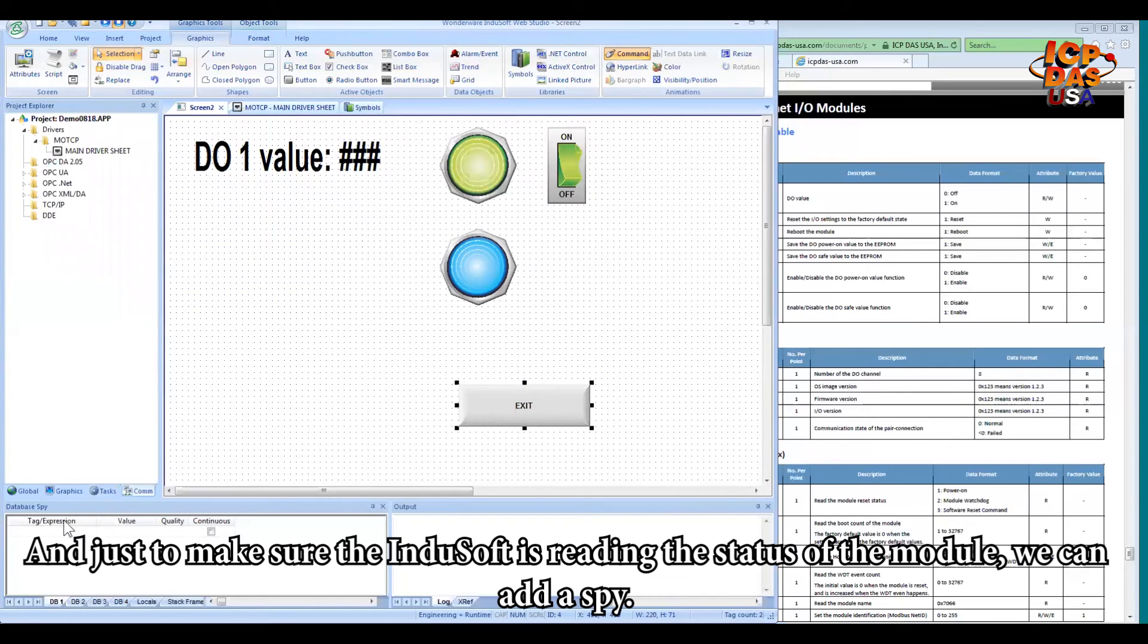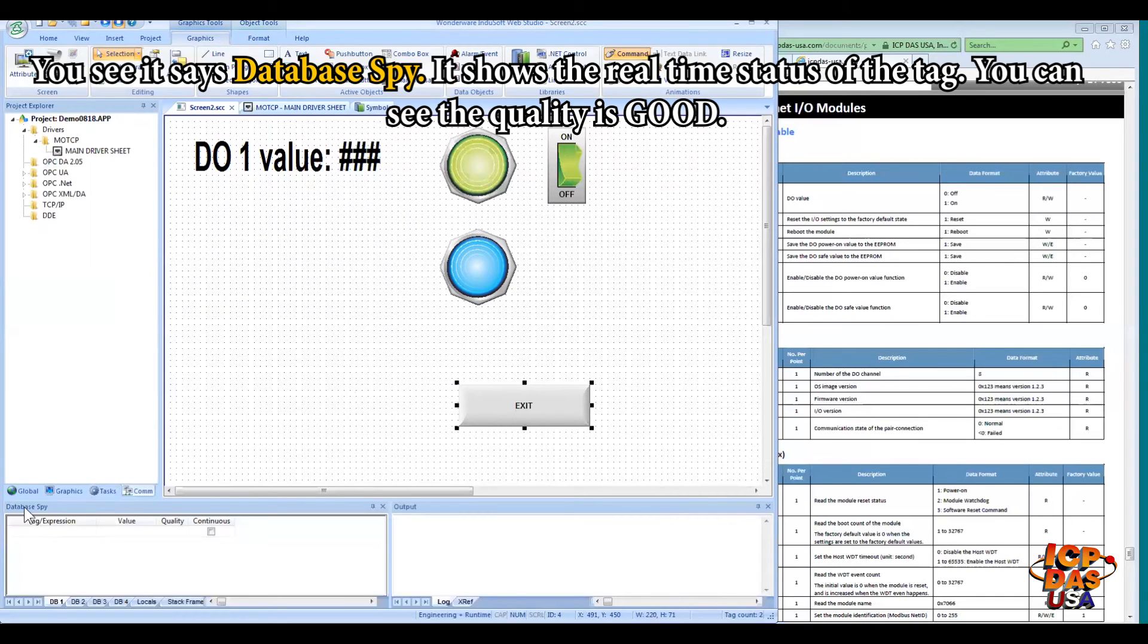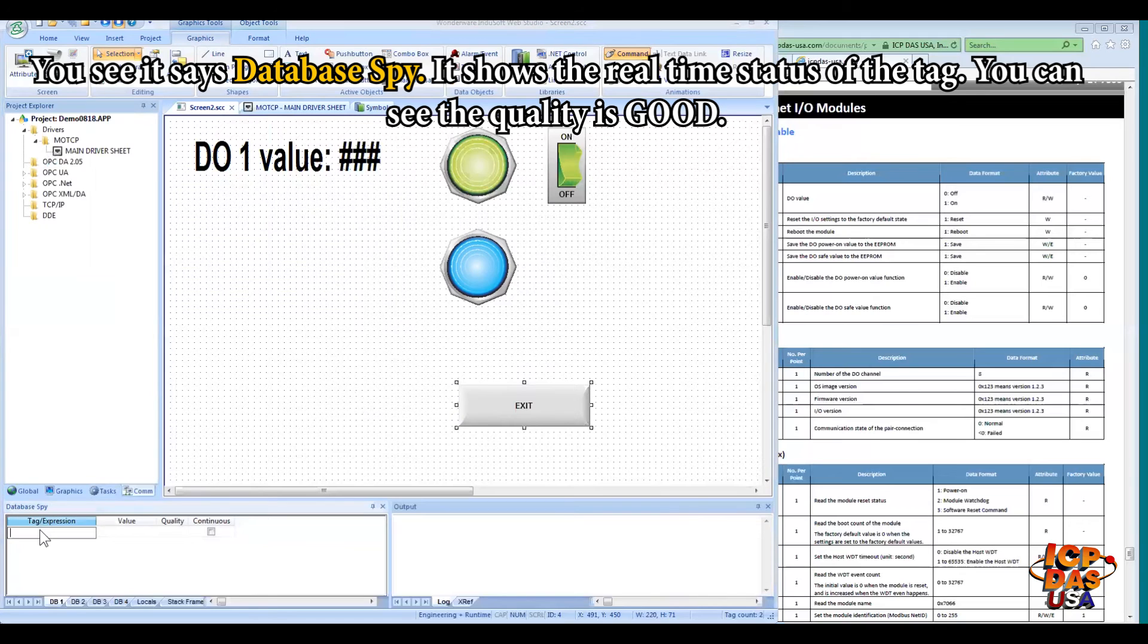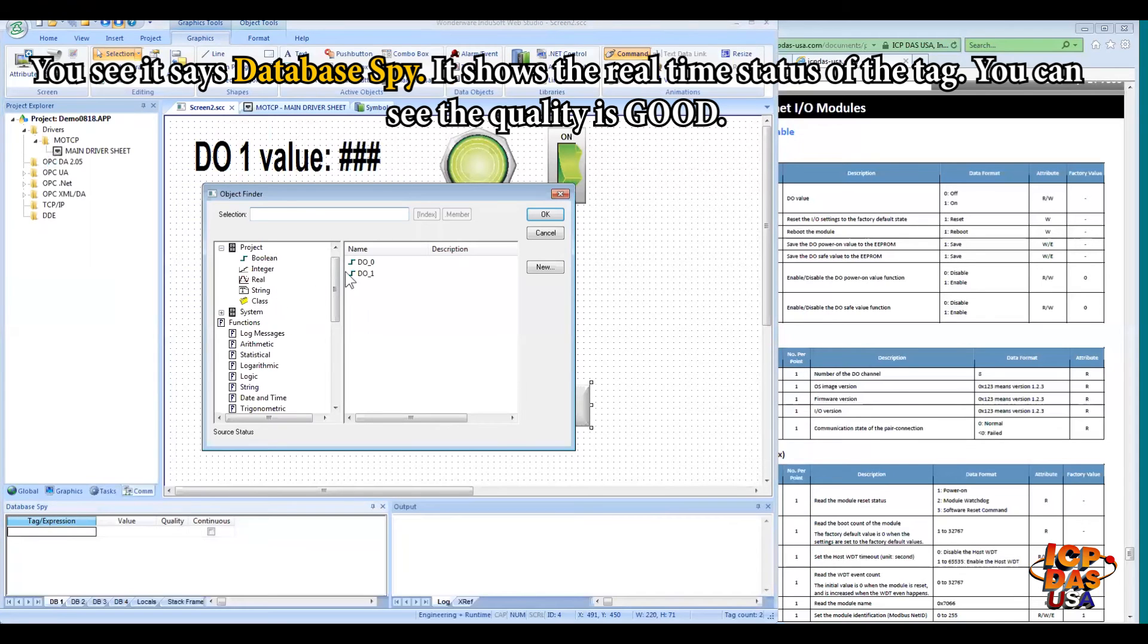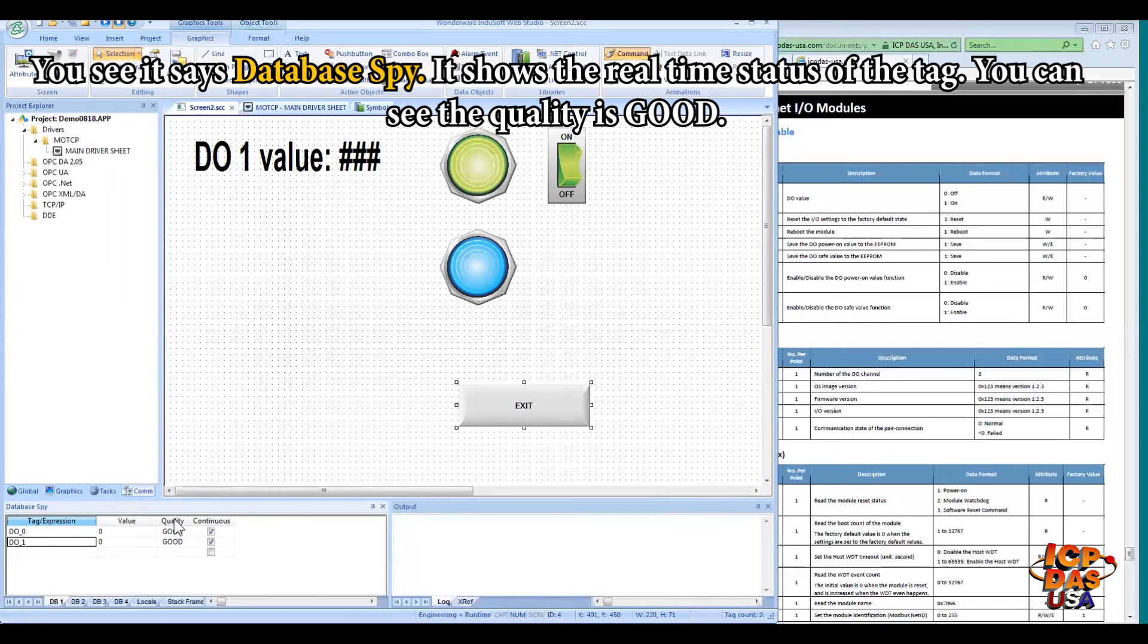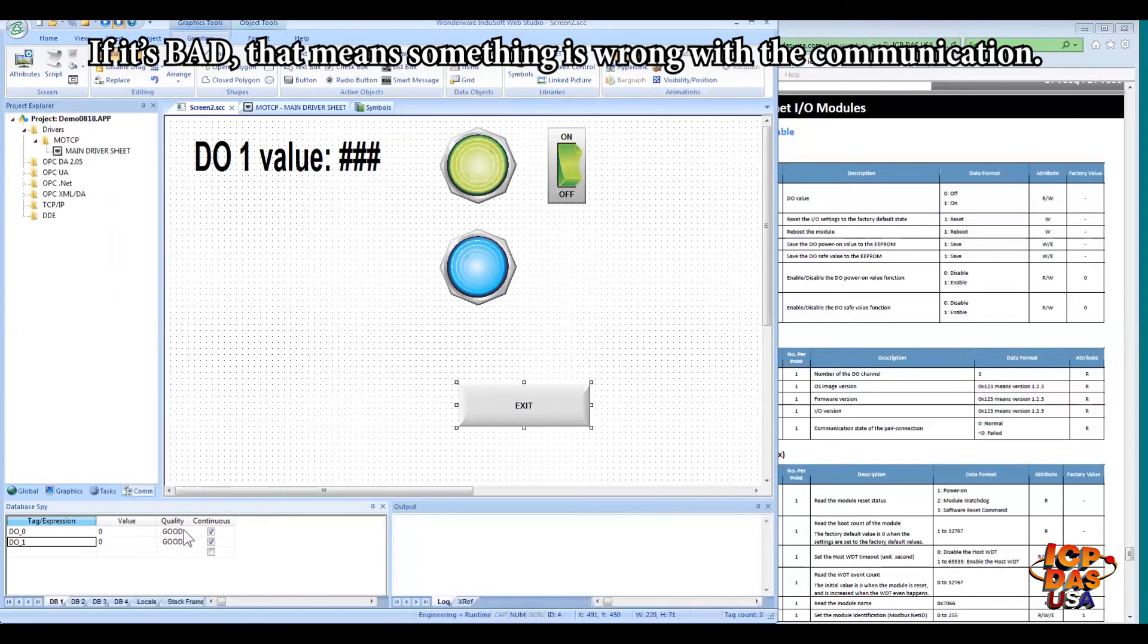And just to make sure the InduSoft is reading the status from the module, we can add a spy. You see that it's called a database spy. OK. You can put it, and it will show the real-time status of the tags. So you will see the quality is good, means the communication is established. And if it's bad, that means something wrong with the communication.